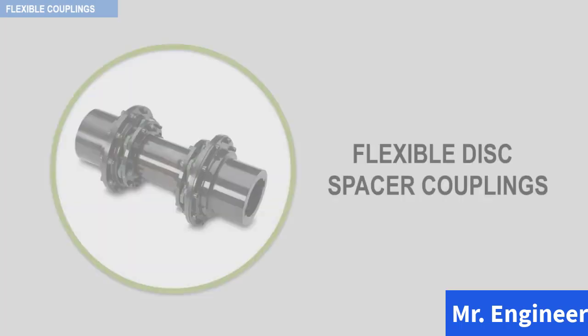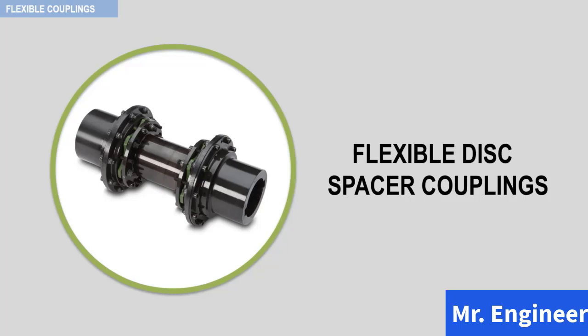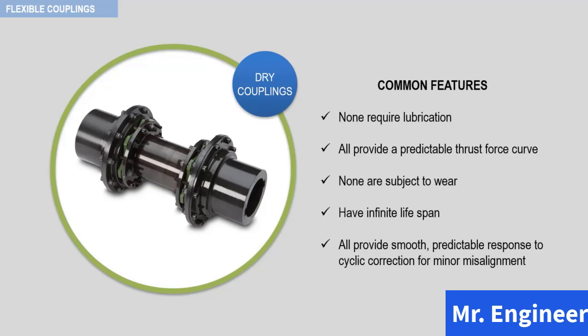Flexible membrane and flexible disc couplings do not have moving parts and derive their flexibility from controlled flexure of specially designed diaphragms or disks. They do not require lubrication and are commonly known as dry couplings. The diaphragms or disks transmit torque from one shaft to the other, just as the gear meshes do in a gear coupling. Common features include: no lubrication required, a predictable thrust force curve for a given axial displacement range, and when properly applied, operated, and maintained, none are subject to wear and have an infinite lifespan.